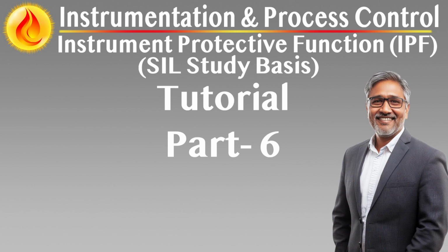Interface testing during commissioning. All communication links must be functionally tested to confirm expected behavior under normal, fault, and degraded conditions. Failure mode evaluation. Systems must be assessed for communication loss, corrupted data, and unexpected responses, ensuring that the IPF always fails safe. Ongoing monitoring and change control.